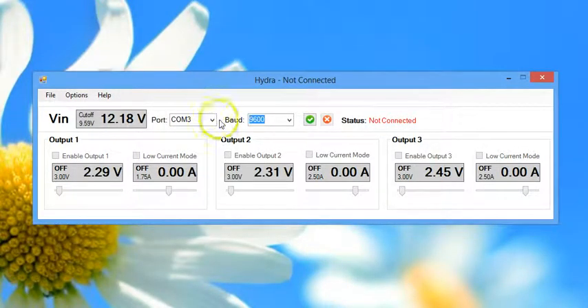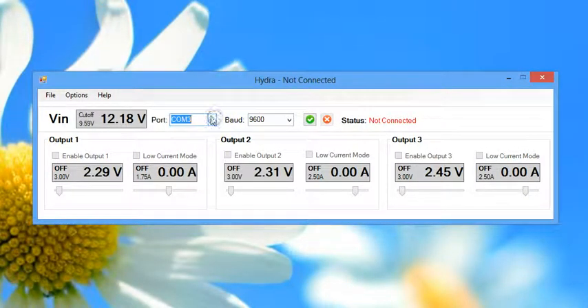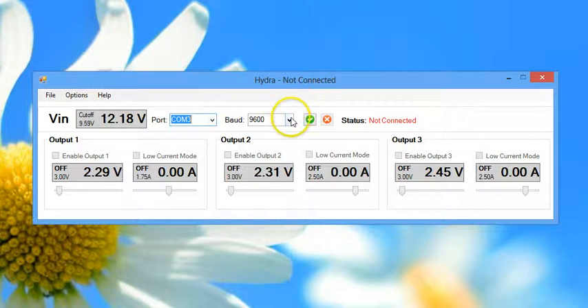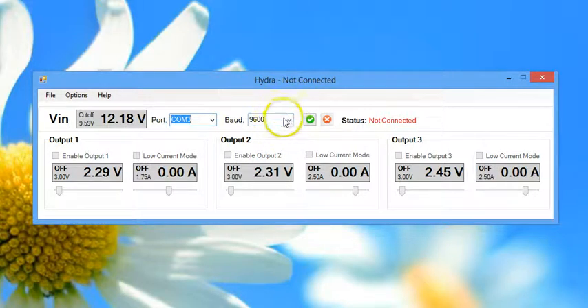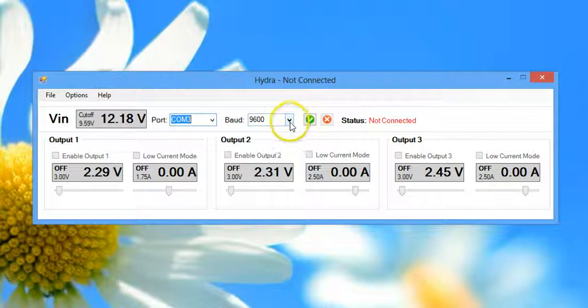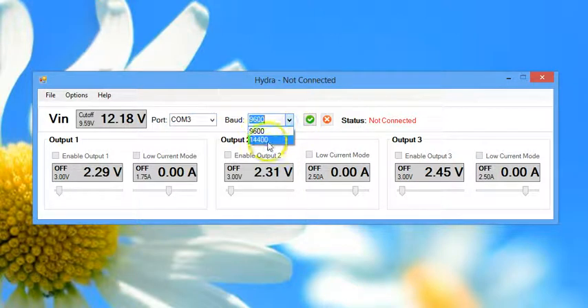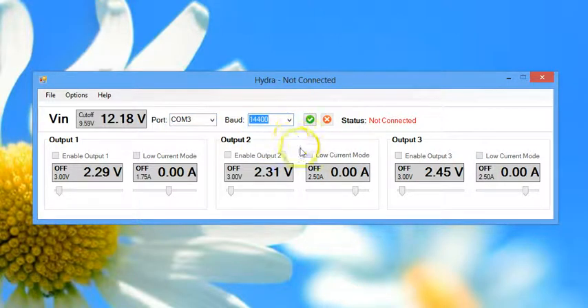On my machine the COM port is COM3, and the default baud rate for all Hydras is actually 9600, except for some of the very first Hydras that were shipped, which shipped with a 14400 baud rate, which is actually what I'm using now.